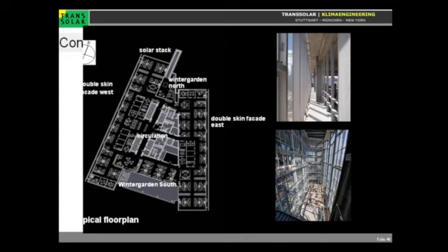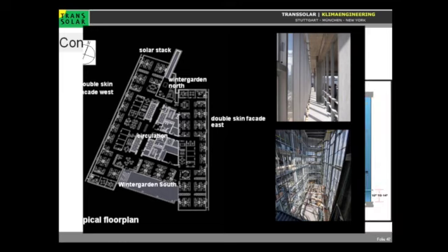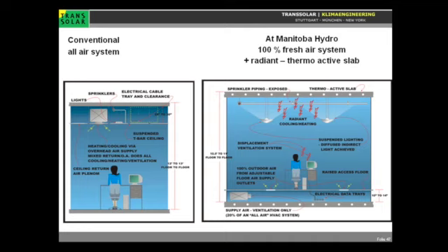The perimeter is a double facade, twice double glazed, because we were a bit afraid of condensation, and there had been some bad experiences with double facades in Canada, leaky buildings getting a lot of condensation or ice in the double facade. So we ended up with two layers of double glazing. People compare the system to a typical suspended ceiling, but here we go to a higher space with a raised floor where you supply the fresh air and have the cabling, and then expose the ceiling with an embedded slab cooling system connected to a geothermal system.